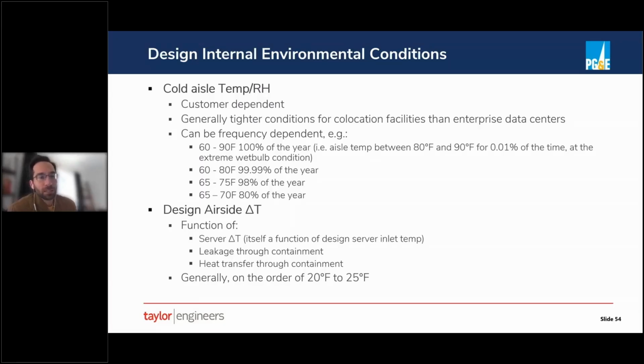The first is leakage across containment. So usually in enterprise facilities, we have, as Jeff was talking about earlier, some level of containment isolating the cold aisles from the hot aisles. Well, that containment is imperfect. So we have some air that, instead of going through the servers, is bleeding through the containment, which in turn lowers the delta T that the air handling equipment sees. We also have a small amount of heat transfer through the containment itself, right? That's usually a small factor, but it also contributes to reducing the airside delta T.